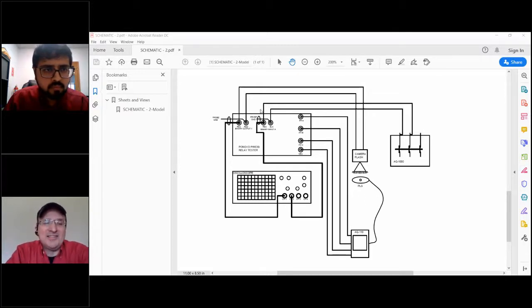Yes, they do. Siemens has an arc quencher called SiQuench, S-I-Q-U-E-N-C-H. You can Google that. It's a medium voltage quencher. It's a very robust device. It's rated for 5 reset operations at full voltage. That device is not yet commercialized for sale in North America. And at present, according to the Siemens product managers, at least as of last week when we were in contact with them, it is not for sale other than in Siemens NX Air IEC switchgear.